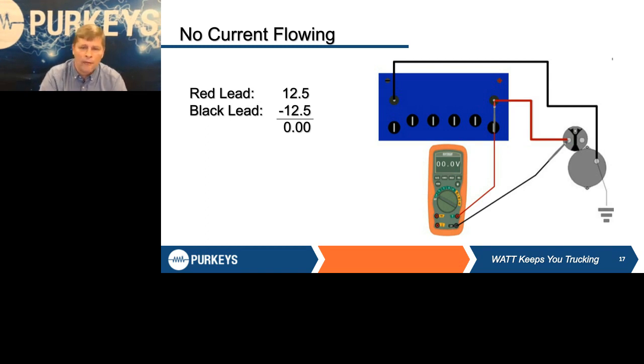But right now I've got them both hooked to positive - the red lead on battery positive, the black lead on starter positive. With no current flow, what does my red lead read? Still 12.5. My black lead at starter positive also reads 12.5. The difference is 0 - there's no difference because we have no current flow and no voltage drop. That's the key: making sure you understand whether or not current is flowing.